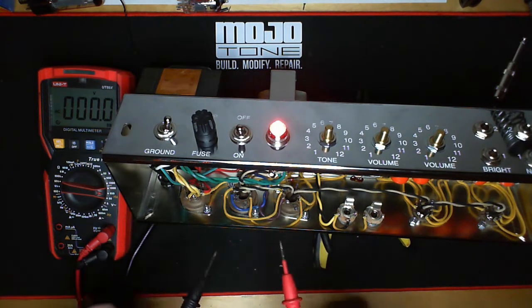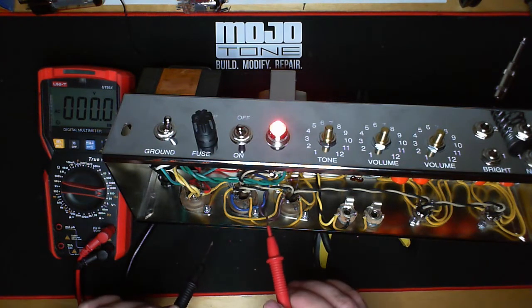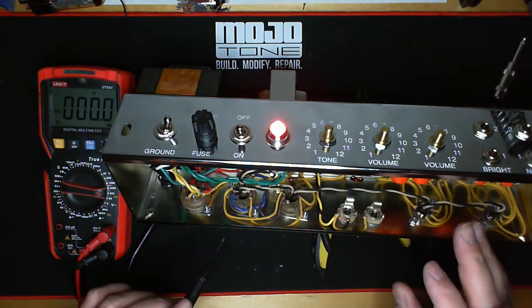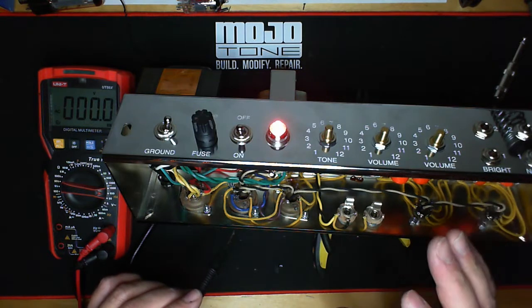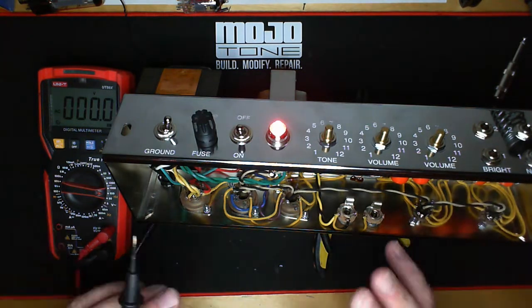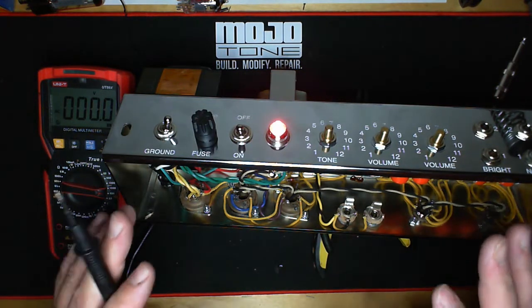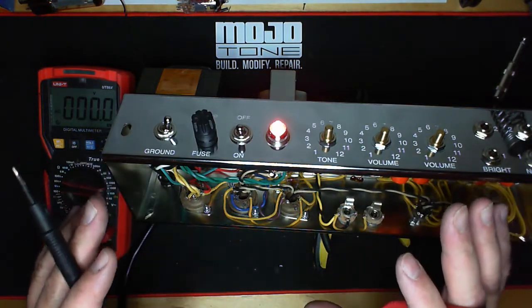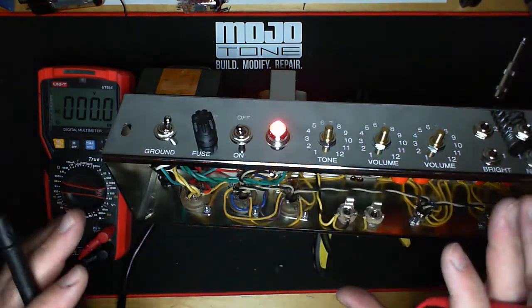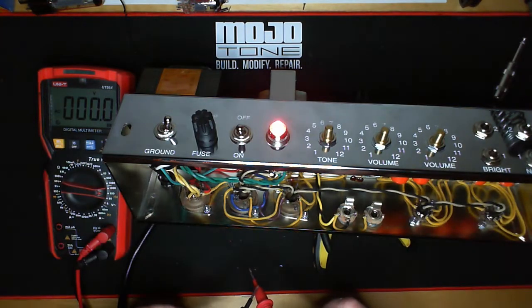That's basically it for checking our secondaries on the transformer. The whole time we're doing this, we're listening for anything unusual, and also smelling to make sure nothing has started burning. If you have a short, that will give it to you right off the bat. You'll smell it before you see it probably.